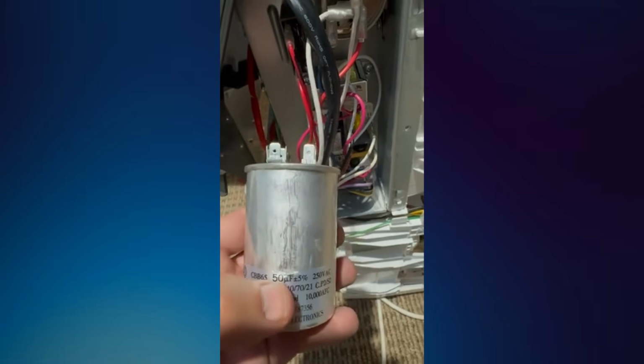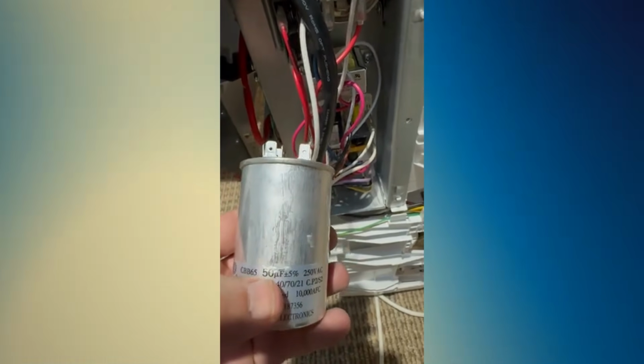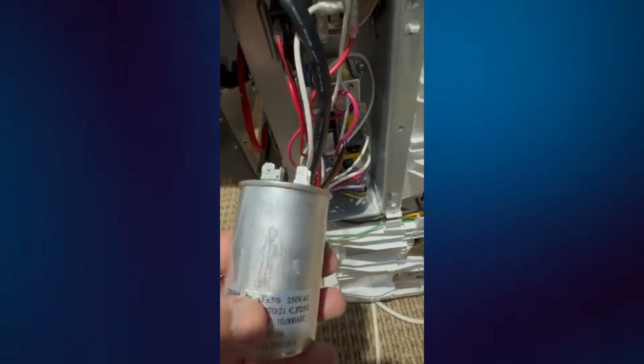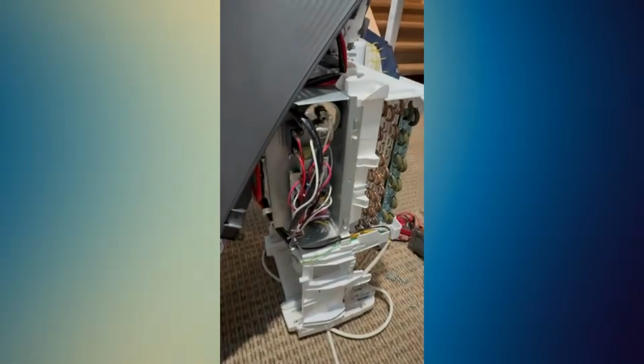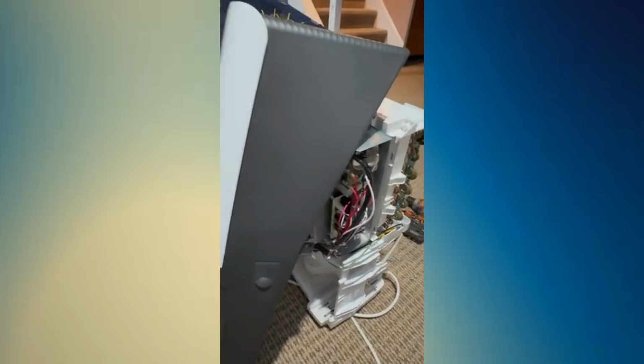Capacitors can retain a dangerous electrical charge even after the dehumidifier has been unplugged. The compressor circuit also operates at mains voltage. For this reason, capacitor testing and replacement should be performed by a qualified technician unless you have appropriate electrical training and test equipment. If the fan runs but the compressor does not start, listen for humming, clicking, or repeated attempts to start.